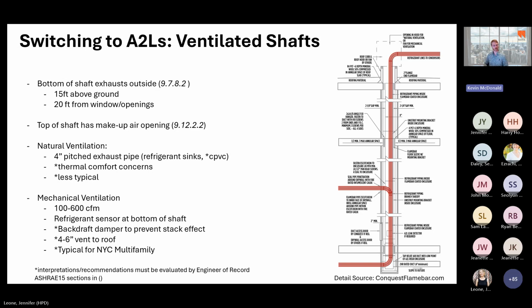So the guidance on this is once again in ASHRAE 15, and there's a lot of nuances here, but you could think of 100 to 600 CFM as kind of typical for most shaft sizes. It's based on velocity. I would recommend a backdraft damper or something integral to the fan, so you don't have stack effect from a thermal and sustainability perspective, with air constantly going through these shafts.